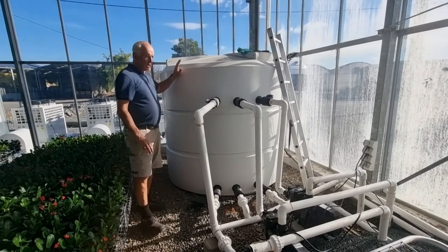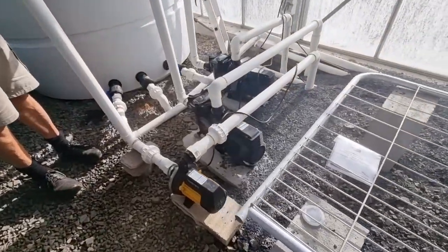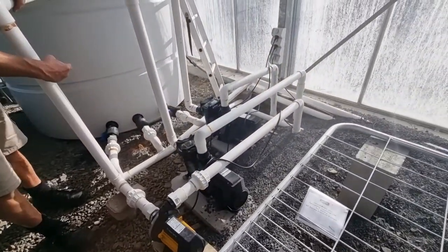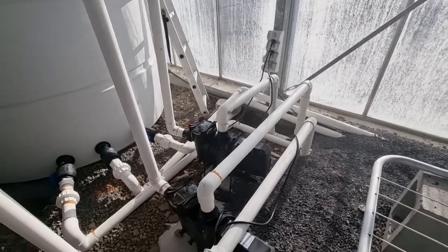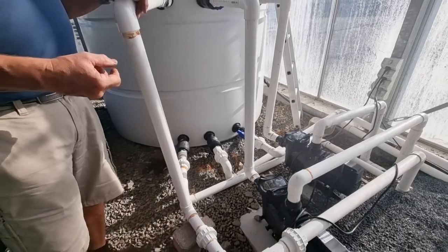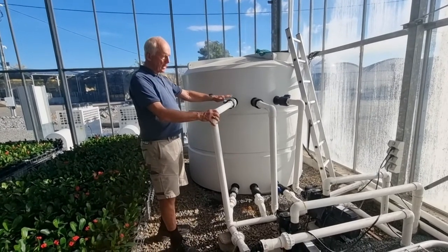From there, I then heat each of the three floors with a separate pump. That will suck the water — the water comes in at the top of the tank, warm. We then take it from the top of the tank, pump it through the circuit, and push it back into the tank through the bottom of it. The water temperature is around 28 to 30 degrees. When it returns, it's probably lost 6 to 7 degrees. The cold water goes to the bottom of the tank. Meanwhile, we're drawing off the warm water at the top. On the reverse side, the heat pumps are drawing the water from the bottom of the tank and pushing it back into the top, at approximately the same level as where we're taking it off here.